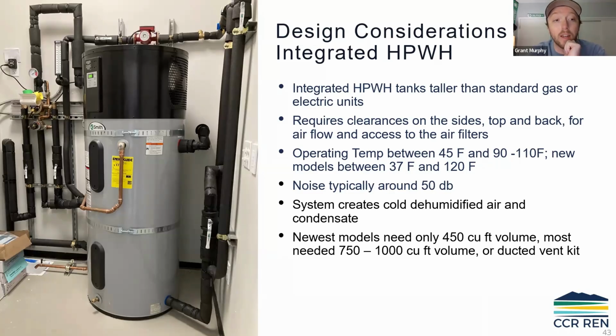And if the system didn't have that type of air volume to pull from, they still have an electric resistance water heater as backup within this. So as soon as that unit didn't recognize that it had the airflow to operate in heat pump mode, it would just kick into electric resistance mode. So a lot of homeowners and installers immediately had a bad reputation surrounding these units because they weren't cheap. And when you install them, they said, hey, my electricity bill went up. These things aren't working well. And what we found is that the vast majority of them were just not installed correctly.